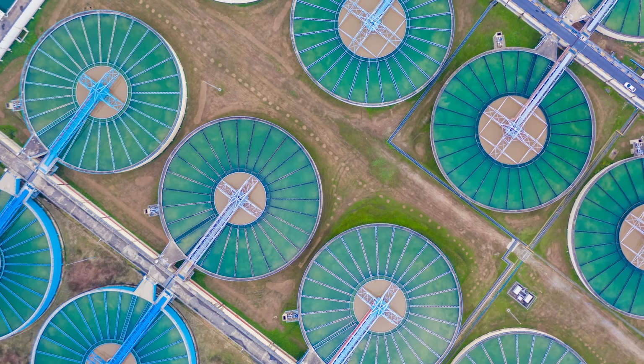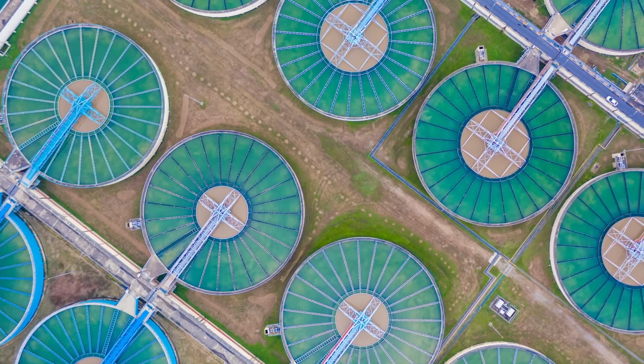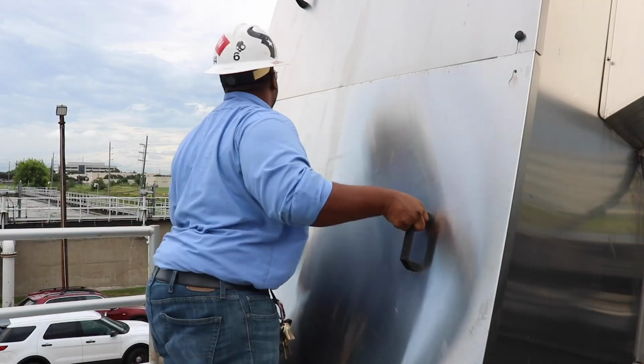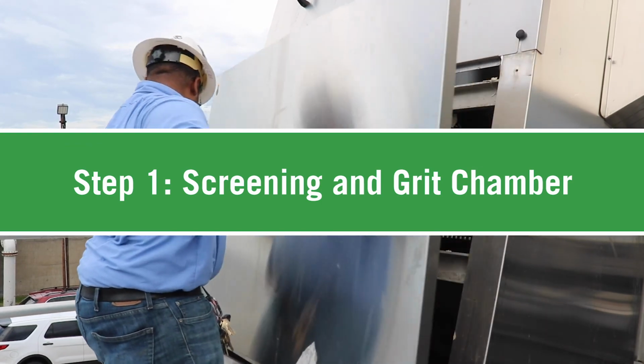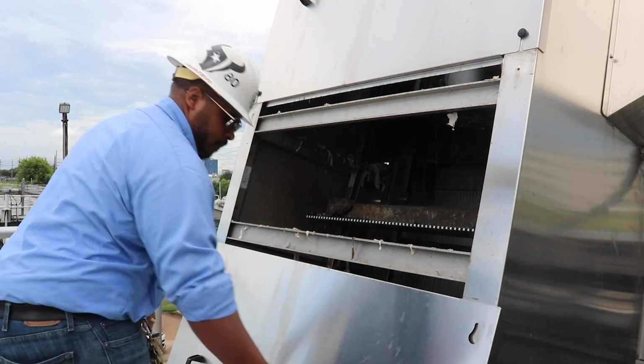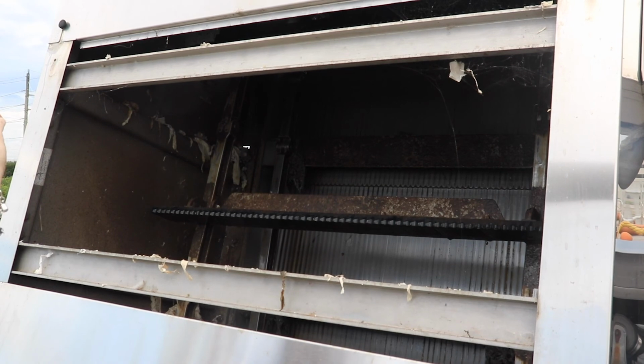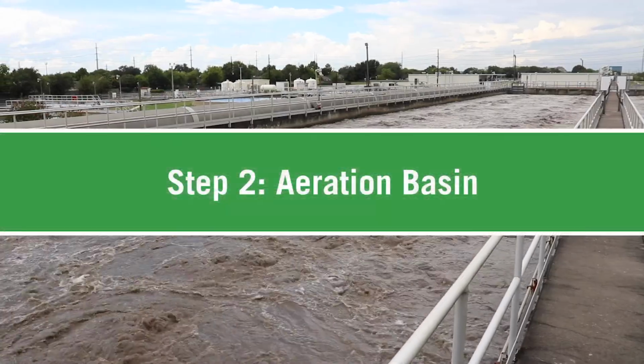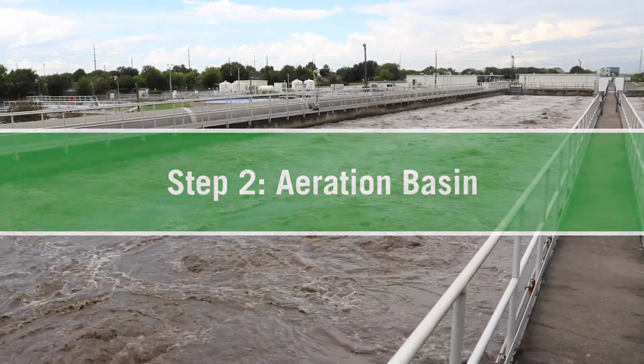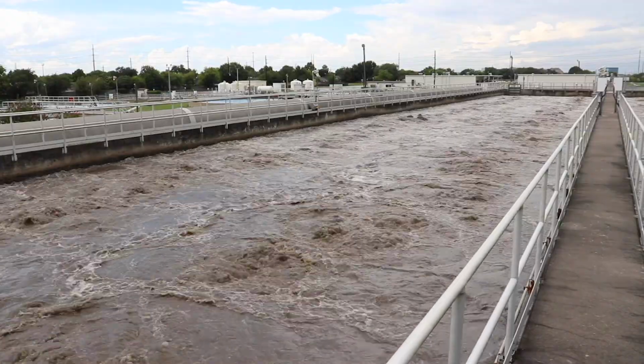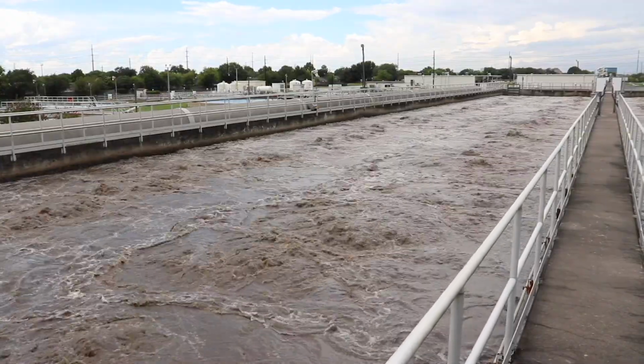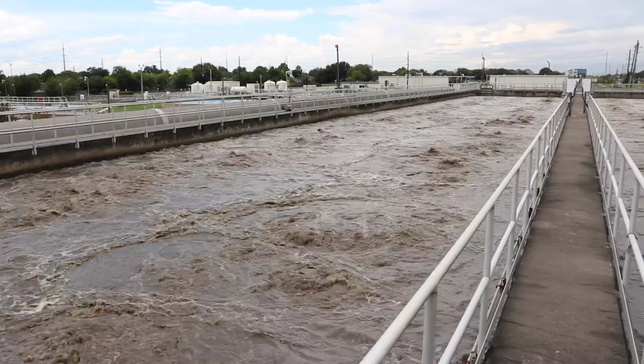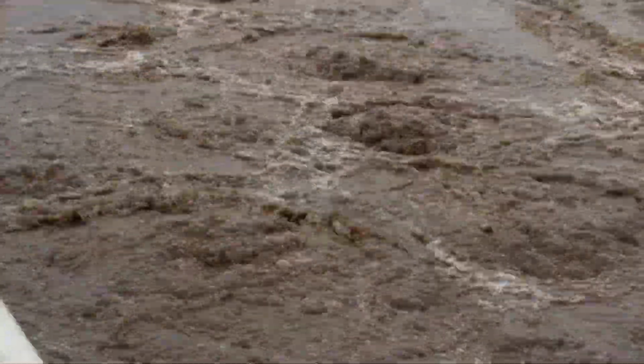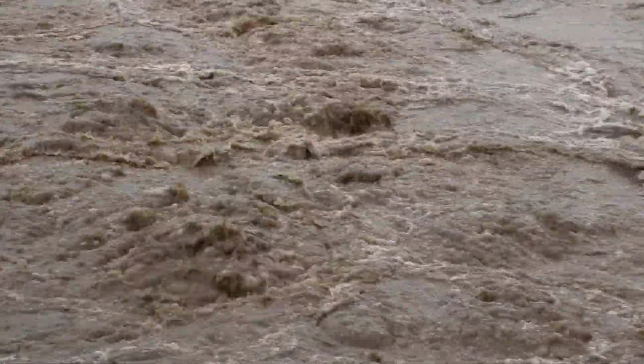A typical water reclamation plant might include the following steps. Step 1. Screening and grit chamber. The wastewater brought into the treatment plant will be screened to remove large debris and grit. Step 2. Aeration Basin. In this part of the wastewater treatment process, bubblers are used to add oxygen to the tank, and microorganisms are used to eat the organic material found in sewage.